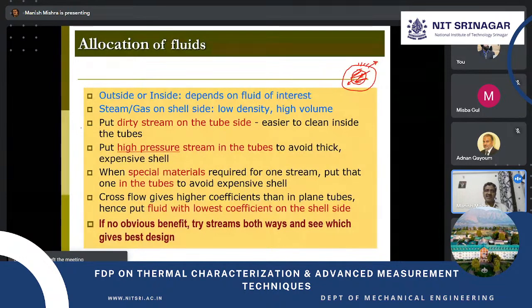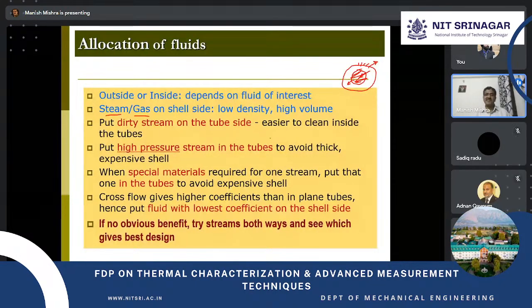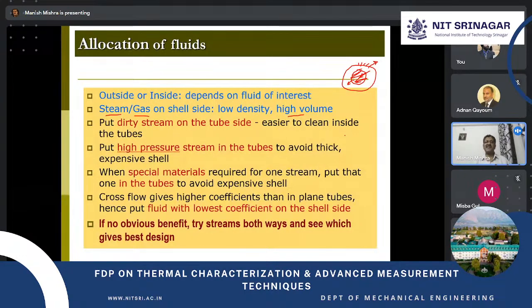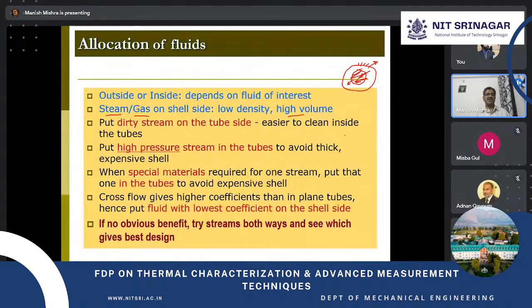Similarly, when one fluid is either steam or gas, how do we decide? Basically it is based on density. Steam or any gaseous fluid, having low density or high specific volume, needs a larger volume for the same mass flow rate. If I provide a tubular passage for that, generally we may not be able to accommodate it unless the length of the heat exchanger is too large. So to avoid that, whenever we have steam or gaseous fluid, it is generally passed through the shell side, in shell and tube heat exchangers. That's the reason the condenser in a thermal power plant is generally a shell and tube heat exchanger.